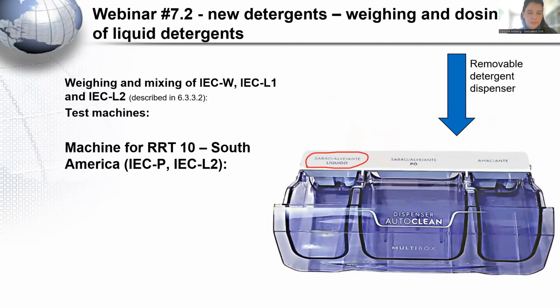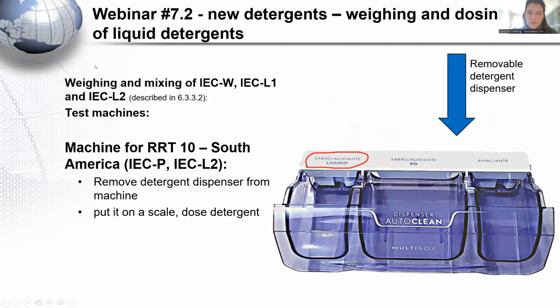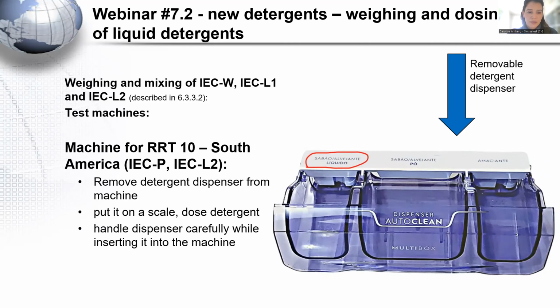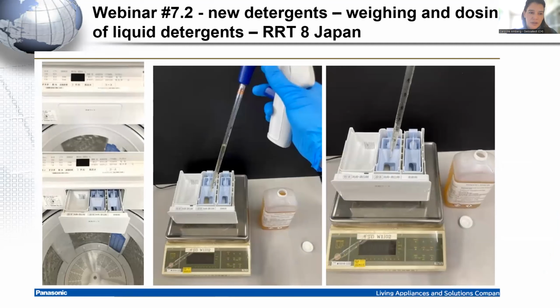Then for the round-robin 10, we also have a good solution. So the detergent dispenser is removable. You can place it on the scale and dose the detergent inside this liquid compartment. It's big enough to hold the amount of detergent needed. And then afterwards, you just put it back into the machine and you can start the test run. For Japan, so the round-robin 8, also a good solution is available. So the detergent drawer can be taken out and the detergent can be directly placed into this detergent drawer on the scale, and afterwards you just put it back into the machine.